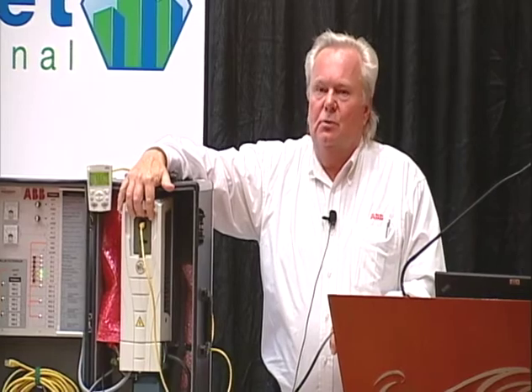And in the industrial world, we often need drive-to-drive communications. The example I always use is conveyors. I've got two conveyors. When this one starts, this one better start, because boxes are feeding from this one onto this one. And the analog output, the speed reference from this one, is telling this one how fast to go. So they go up and down in speed together so I don't get boxes falling off all over the floor because one's running faster than the other, right?